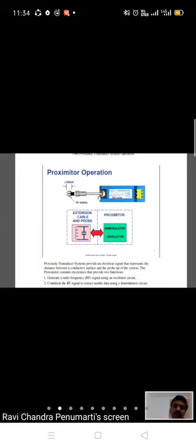This is a special probe which carries the signal up to the target. I have photographs on other pages, sir. So this is basically the Proximitor. It consists of a demodulator and an oscillator. And this probe is a special probe, and you can represent that probe in capacitance and inductance form like this: extension cable and probe.